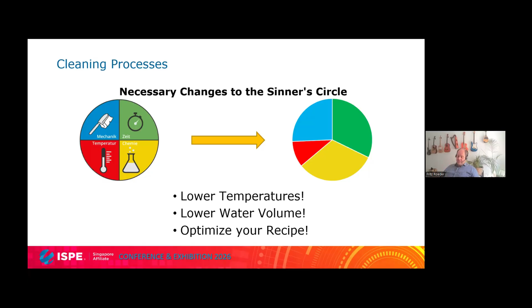One more topic that's quite interesting, something we've done in a new building. Typically, when you perform a final rinse of a vessel, you have a once-through final rinse: you put 200 liters of purified water or water for injection into the vessel and just let it drain to the waste.